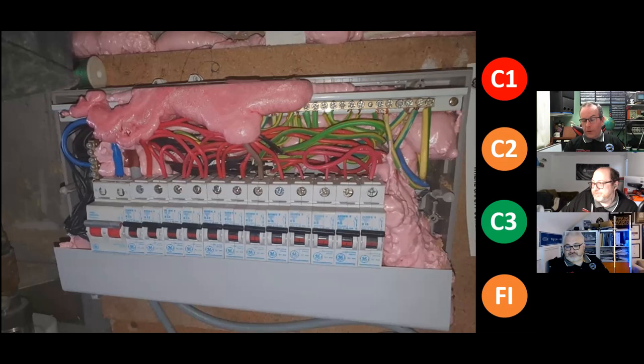And the other thing, you've got no RCDs there whatsoever, so it's obviously a fairly old installation, so there's going to be other things that don't comply. So that's late 90s, that is. I remember them boards well. They were very popular in Screwfix. There we go. Okay, 70% C2, when GE did boards. Got 70% C2 on this, 18% C1.